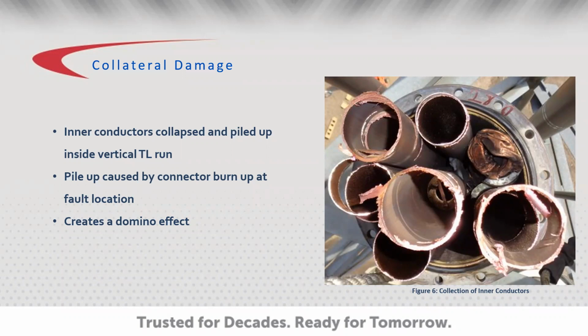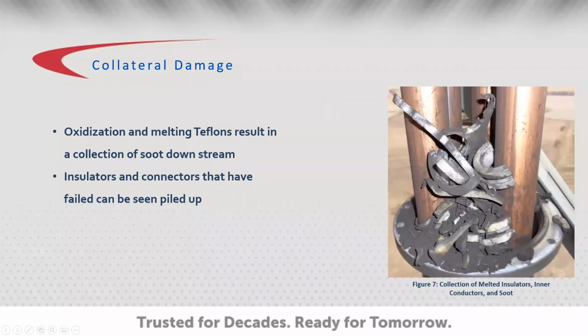Actually, when they were going to take the flange apart, they weren't able to undo the bolts and pull it off. They had to use a Sawzall and just cut right through the tube, and then they found that. It's an interesting find, I would think. All right, this figure 7 shows the collection of all the melted insulators stacked inside around the inner conductors inside the outer, and all the pile of soot that resulted from the combustion that took place inside the line.